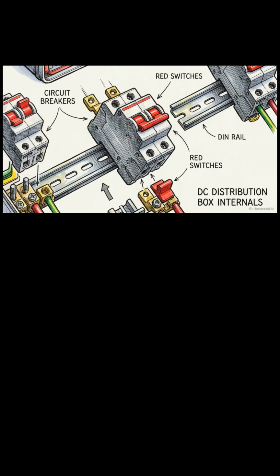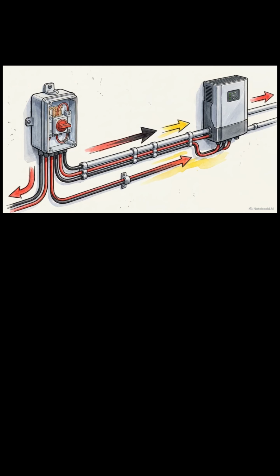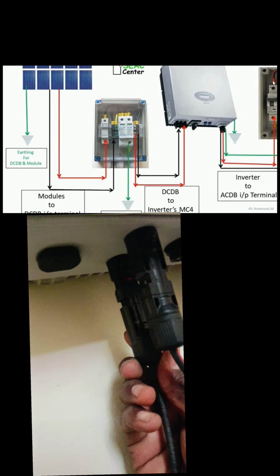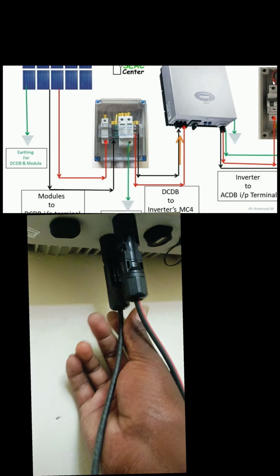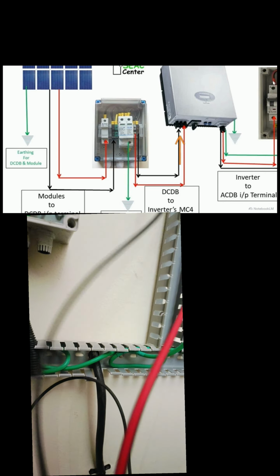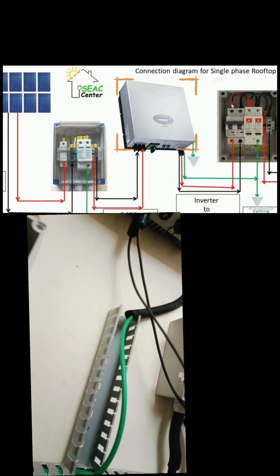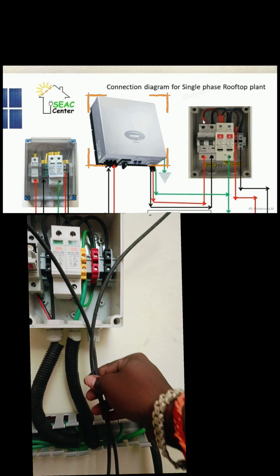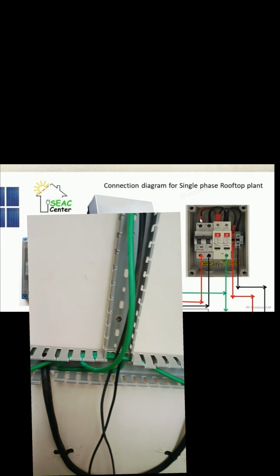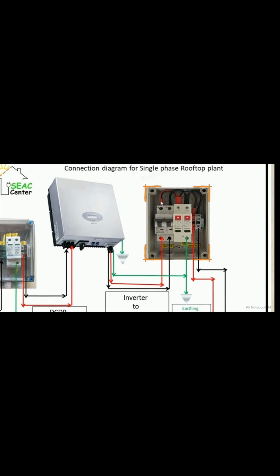This box acts as your first defensive barrier. It intercepts the raw, highly variable direct current coming from the sun and isolates it, protecting your sensitive conversion equipment down the line from sudden power spikes. Tracing the DC power from the DCDB, we connect to the single-phase inverter using weatherproof MC4 connectors. This inverter transforms raw DC energy into usable alternating current. From its output, we route the converted AC power directly into the alternating current distribution box.